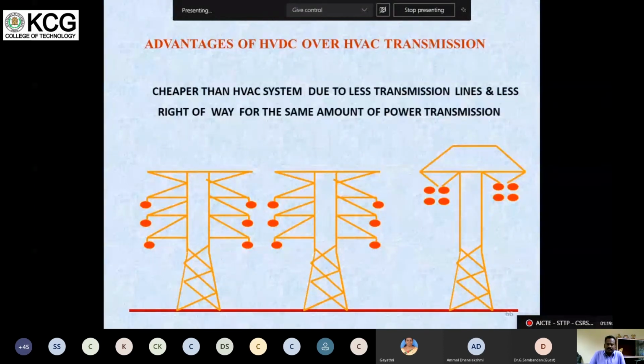So it is cheaper than the HVAC system due to fewer transmission lines and less right of way for the same amount of power transmission. You can see there are 2 towers used for transfer of 2000 megawatt. With only 1 tower we can transfer power of 2000 to 2500 megawatt, or nowadays up to 6000 megawatt is possible. So you can assume the number of conductors is reduced, the number of insulator strings is reduced, and land cost is also reduced.